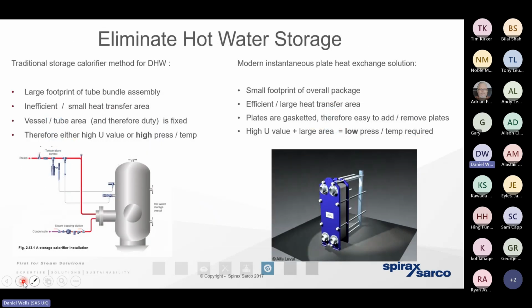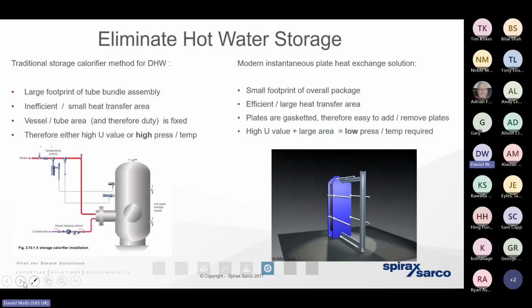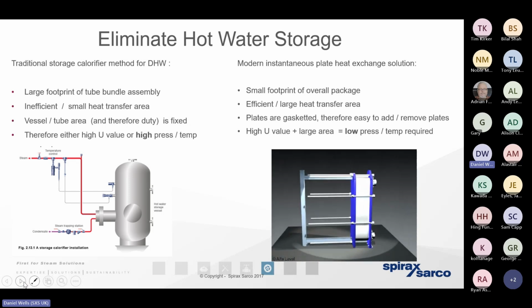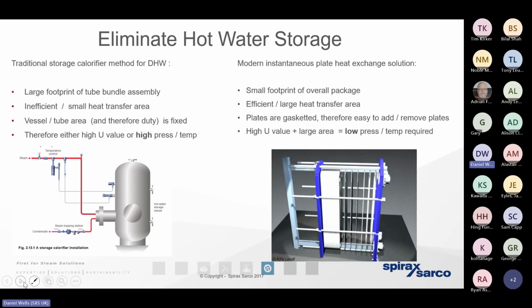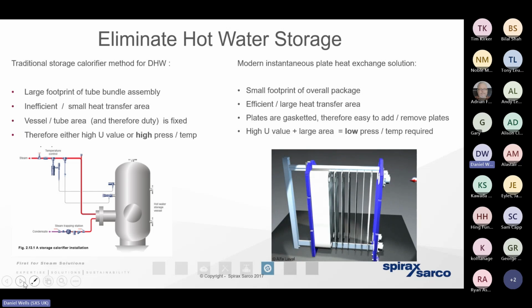Okay, so we looked at the topic of heat exchangers some weeks ago now. I just really wanted to loop back to this topic because there are going to be significant energy improvement benefits if we can move away from the issue of holding hot water in storage and instead move towards a heat exchange solution that is generating hot water from steam instantaneously and on demand. Benefits, well, we don't have the issue of an inefficiency through the overproduction of too much hot water that's never likely to be used.